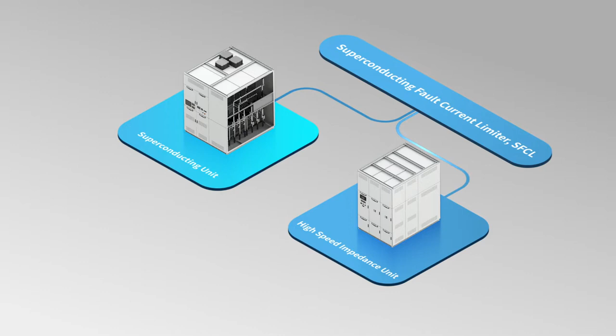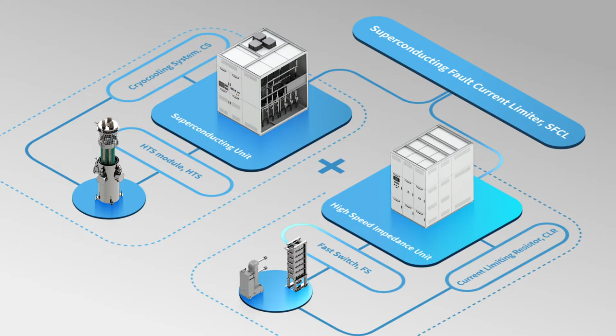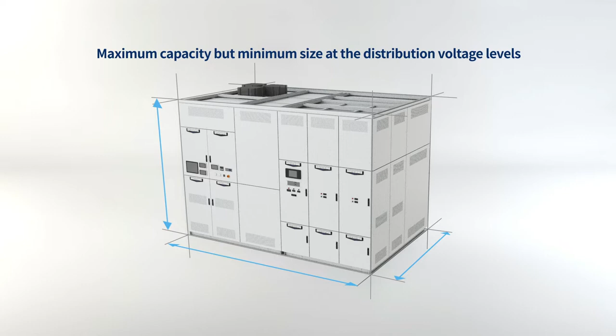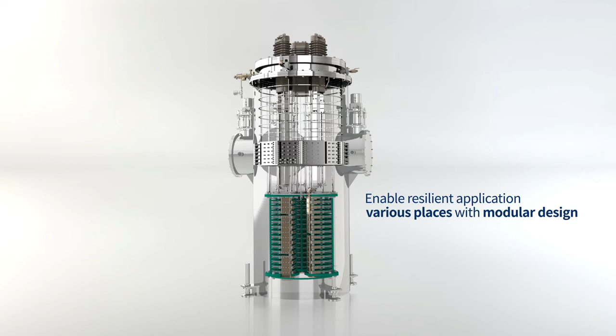SFCL is composed of a superconducting unit in charge of current limitation at the half cycle of the fault current, the first peak of the fault current, and the high-speed impedance unit in charge of fault current limitation after the half cycle. With this composition, LS Electric has successfully developed SFCL, the smallest size, but boasting maximum capacity at the distribution voltage levels. Especially, LS Electric's SFCL is easy to install without any spatial restrictions. And its modular design enables resilient applications in various places.